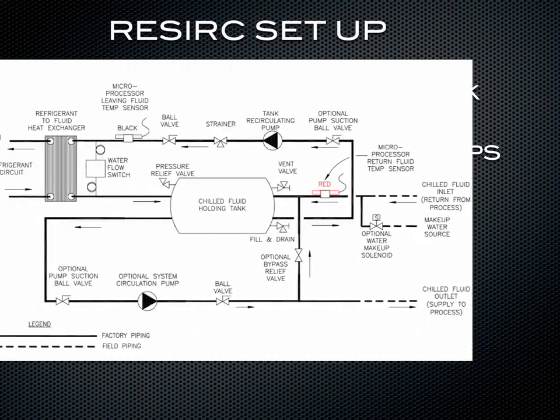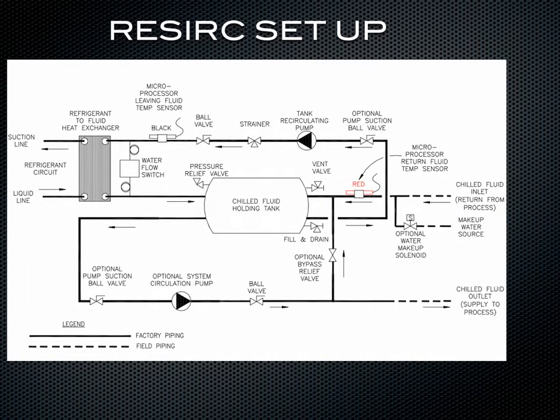Let's get into the drawing of a recirc tank. The tank has four connections — two in and two out. Your piece of equipment is going to generate heat, and that heat will be transferred out of the water. That warm water is brought back to the tank, which is always kept at 55°F. The warm fluid mixes with the tank water that's been chilled, and then you have your desired leaving water temperature going back out to your process through the system pump. That's the first loop.